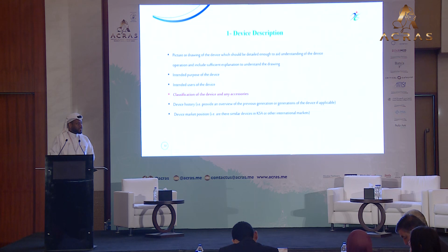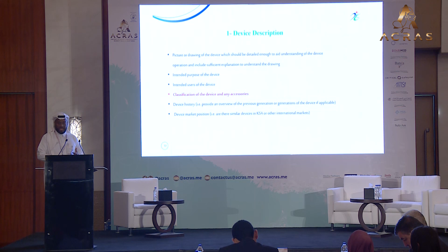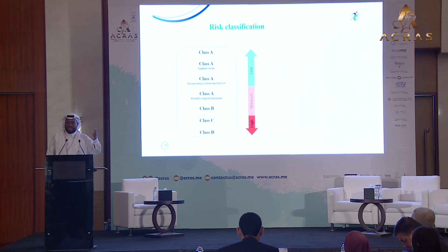If there is an equivalent in the market, it will be much easier to assess, a faster route. But if it's an innovative device, that will take some time, and it will also involve the verification and validation part, which will be in the next few slides. It will take more technical information, lab results, clinical trials, a lot of information. The classification: we have 4 classes, from Class A all the way to Class D, where Class A is any device that doesn't have a measuring function or a sterile symbol, to say it that way. So these are considered medical device Class A, all the way to Class D, where you will have powerful, invasive devices like stents, pacemakers, and so on.